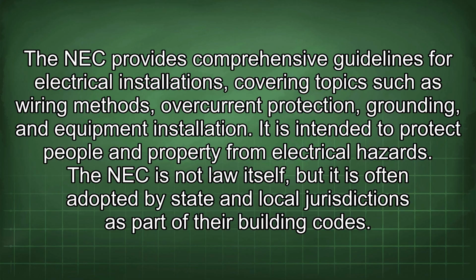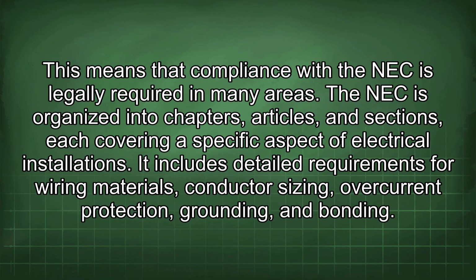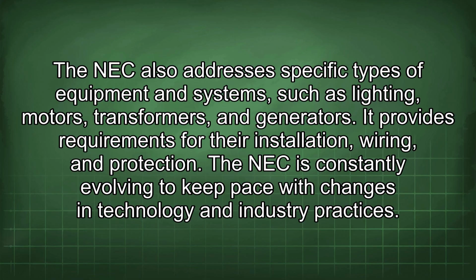The NEC is not law itself, but it is often adopted by state and local jurisdictions as part of their building codes. This means that compliance with the NEC is legally required in many areas. The NEC is organized into chapters, articles, and sections, each covering a specific aspect of electrical installations. It includes detailed requirements for wiring materials, conductor sizing, overcurrent protection, grounding, and bonding. The NEC also addresses specific types of equipment and systems such as lighting, motors, transformers, and generators. It provides requirements for their installation, wiring, and protection.